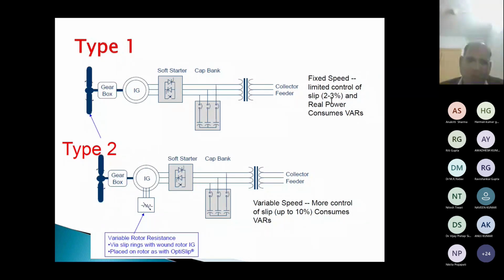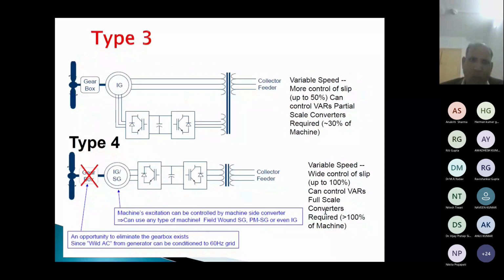So type 1 is almost fixed speed. There is limited control of slip, just like 2% to 3%. So we cannot have much control on the real and reactive power. With the adding of this resistance in the rotor circuit, we have more control on the slip, up to 10%. It means we can control more reactive power. Control of reactive power means that we can control the variation in the voltage, particularly during the fault conditions.